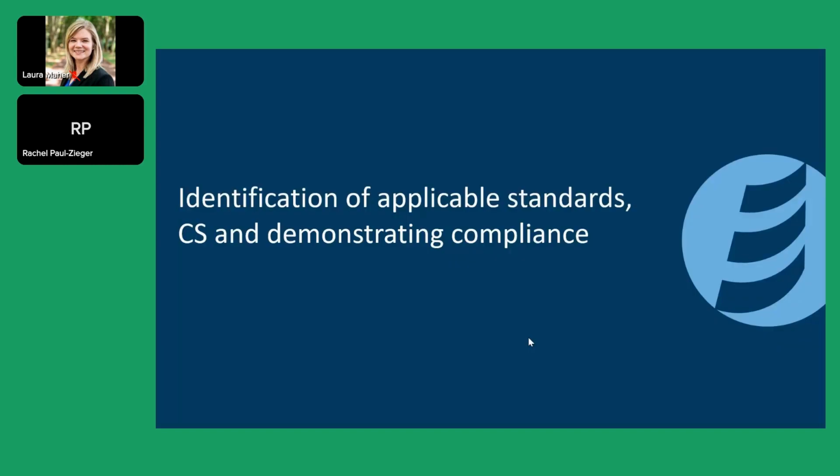So how does it work? How can we demonstrate compliance to the GSPR? The key approach is that first, it should be identified what the applicable standards to the device are. If there are common specifications, we will review what in fact a common specification is, but also some guidance that can be used to demonstrate compliance.